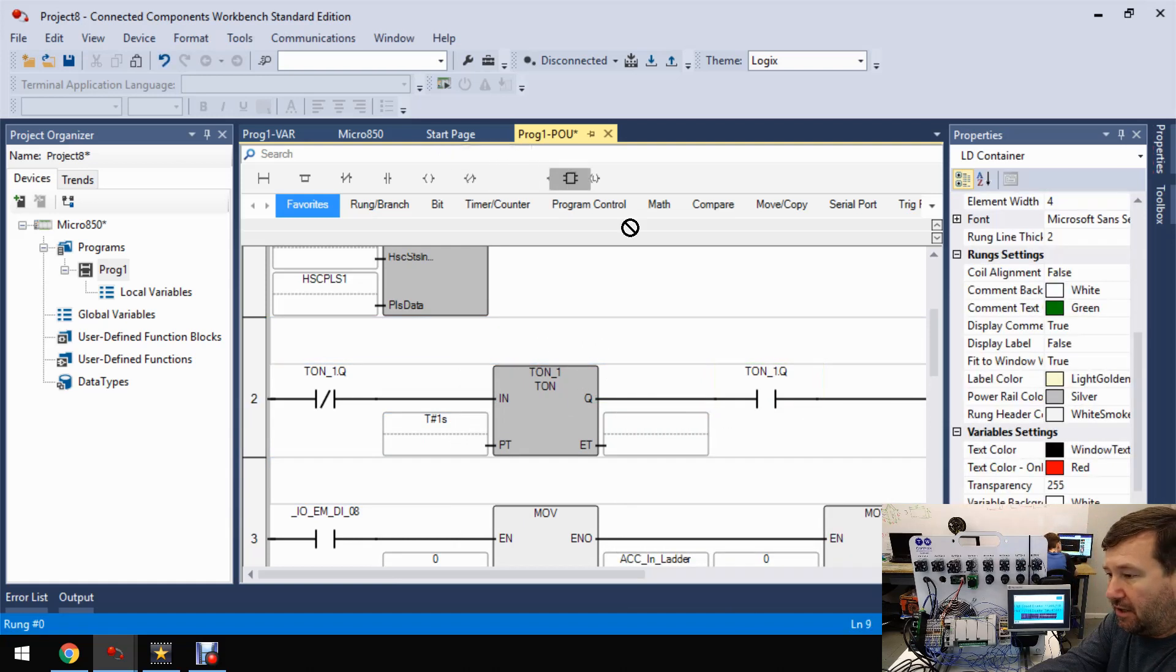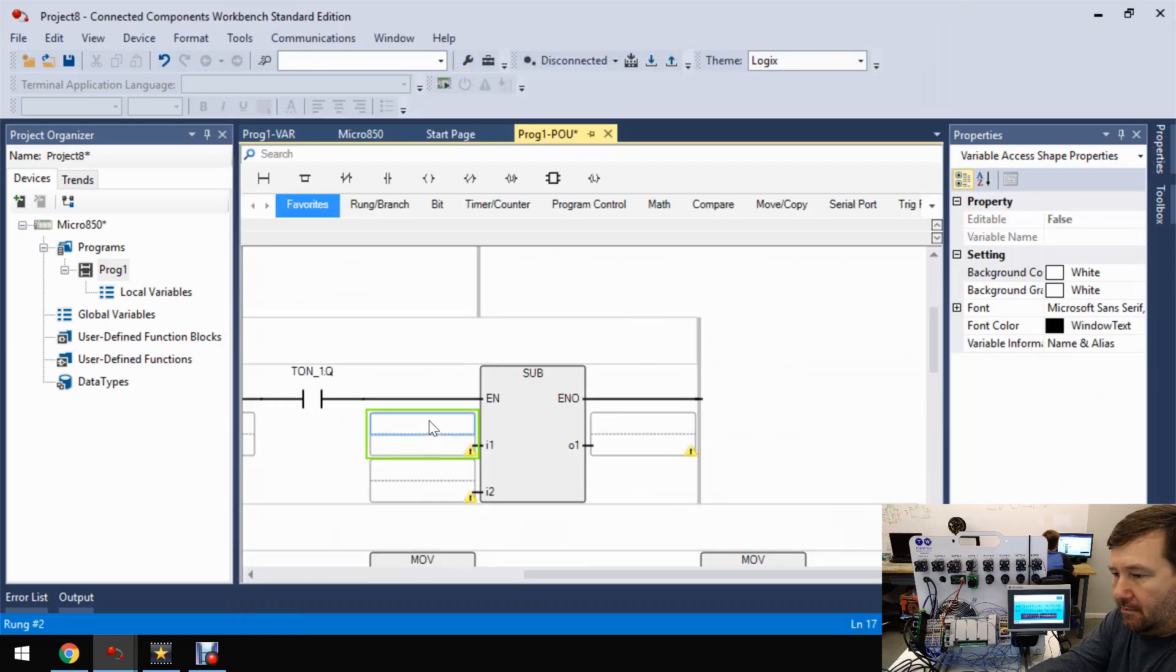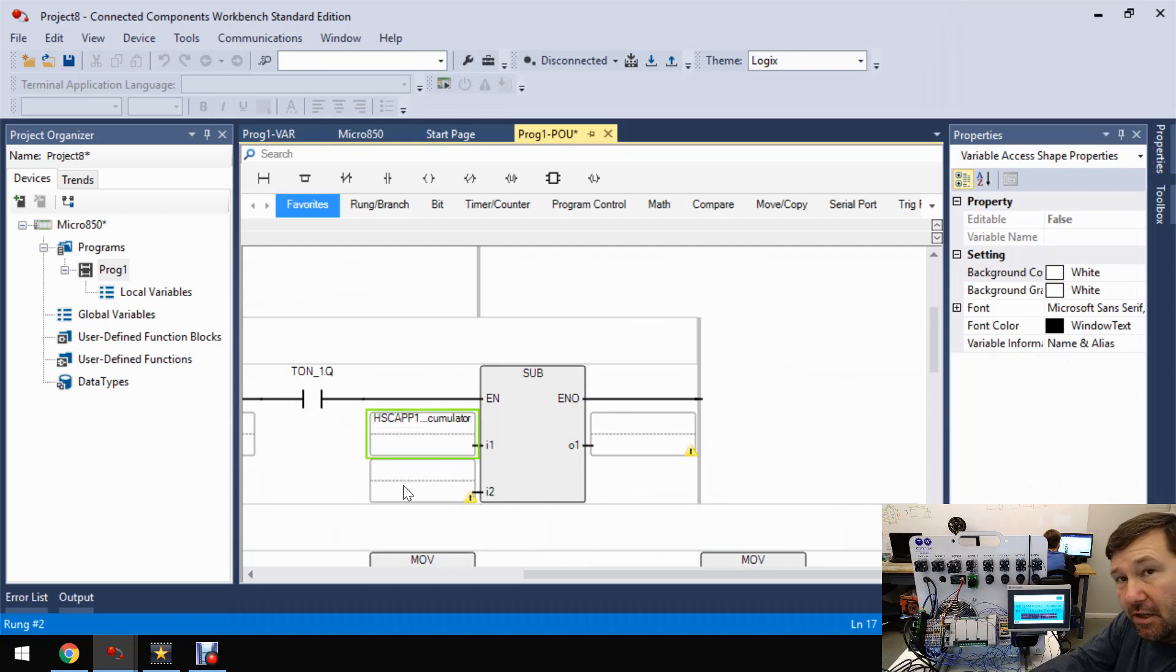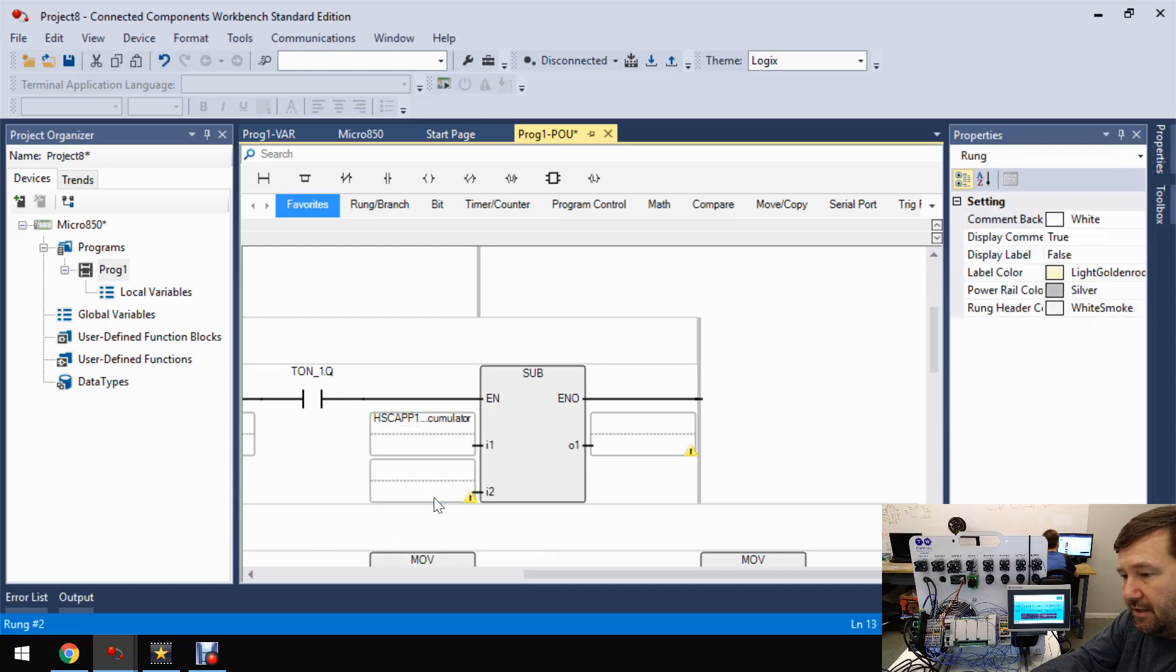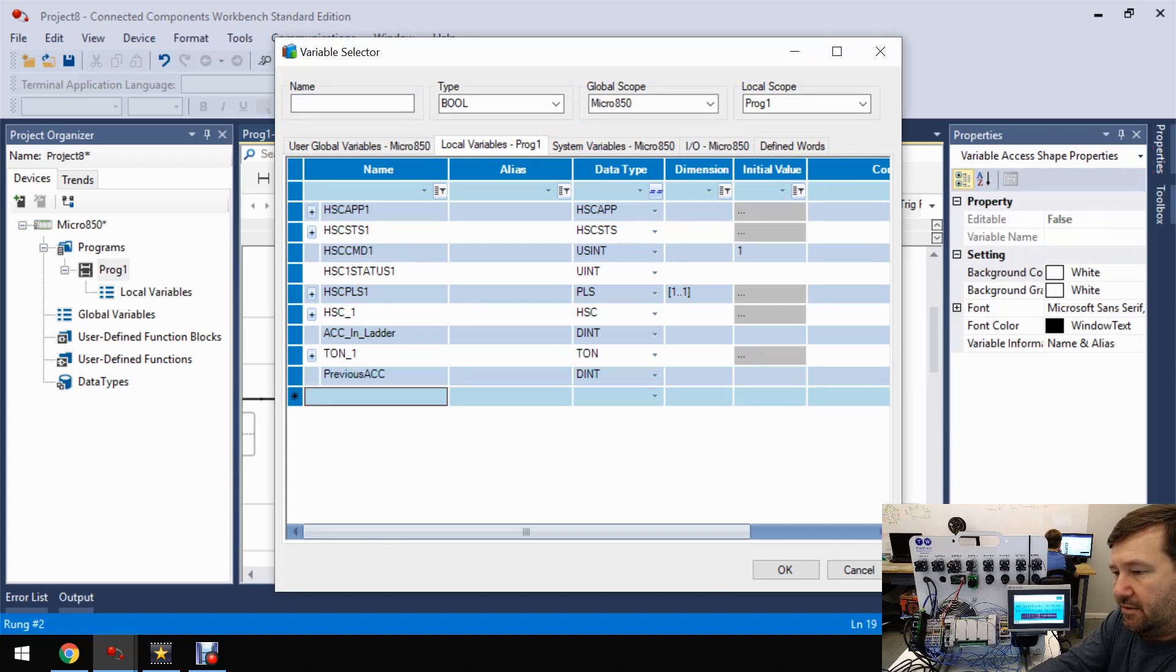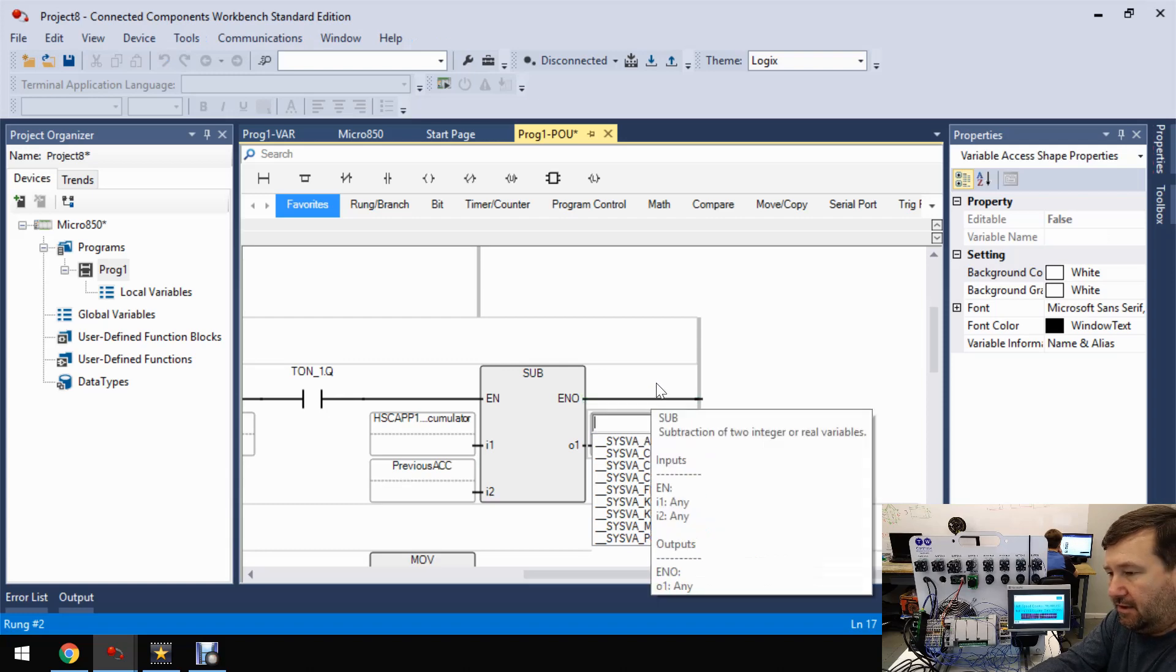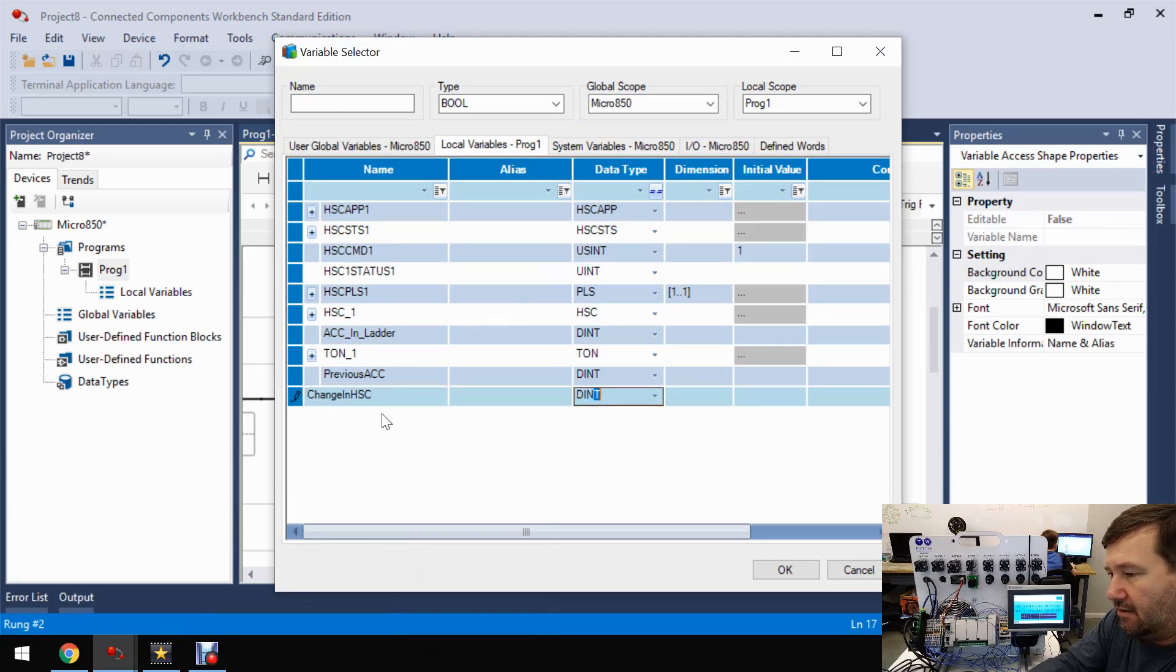So next we're going to bring an instruction block down and we're going to use a SUB or subtraction. And our input one is going to be our high speed counter app one dot accumulator. That's our accumulated value. And then this one, we're actually going to have to create a tag here. We'll just call this previous ACC. And that's going to be a double integer. So we'll select that one. And then our result, we're going to put in another one that we're going to create. Let's just call it change in HSC. And that'll also be a double integer.